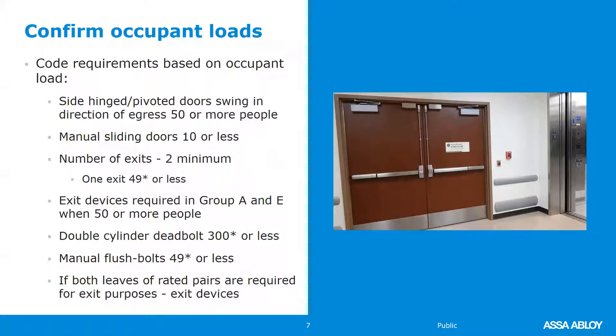How can you tell if both leaves are required for exit purposes? That's based on the occupant load. A three-foot-wide door hung on butt hinges, pivots, or continuous hinges has 33 inches of clear opening space. Based on a table in Chapter 10 of Means of Egress, a three-foot door can exit 165 people in a non-sprinklered building. If you have more than 165, you'll have to use both leaves of the pair of doors for egress purposes.